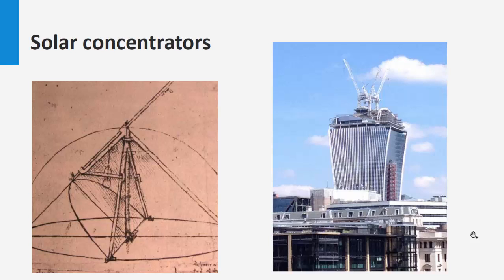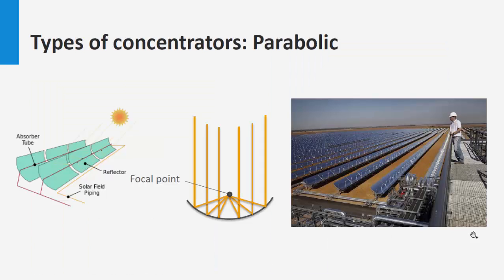The first system we will discuss is parabolic trough collectors. A parabolic trough consists of a linear parabolic reflector that concentrates light onto an absorber tube located in the middle of the parabolic mirror, in which the working fluid is located. The fluid is heated to 150 to 350 degrees Celsius and then used in a heat engine.